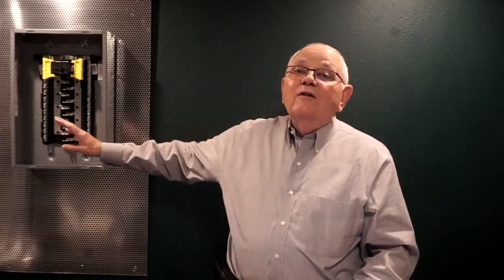If we take a look in Article 100, 70E defines for us an electrical shock hazard. An electrical shock hazard is when we're exposed to energized circuit parts or conductors. Obviously, if this were energized behind me, that would be exposed circuit parts, wouldn't it? Now, a conductor with insulation on it is not an exposed energized conductor. It's an insulated conductor, so I'm not exposed to a shock hazard. If you take a look at this panel, up at the top are the barriers where the main power comes in to go to the main breaker on the line side. And so I'm protected by that barrier from inadvertent contact. If I'm in here doing something, I don't inadvertently touch the main power terminals coming into this panel board.